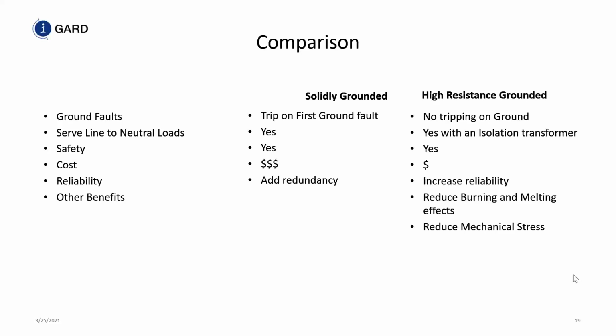We reduce mechanical stresses. This is when you have bracing in your electrical system. You still have to brace for the 3-phase bolted fault current, but not necessarily for a single phase to ground fault. Reduce arc flash hazard to personnel. So that's a bonus because now you're protecting your employees by having a resistance grounded system. And as I said earlier, when you put in any one of those other ground or arc flash mitigation techniques, they only start to work after the fault occurs. Resistance grounding is the only arc flash mitigation technique which limits the energy, or gives you the benefits of using a high resistance grounded system, before the fault occurs.